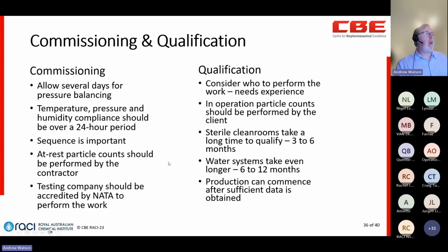Another thing, particle counts. The at-rest particle counts, so that's without the actual operations of the facility, should be performed by the contractor, whereas under qualification, the in-operation particle counts should be performed by the client, because only you know how the facility is operated.